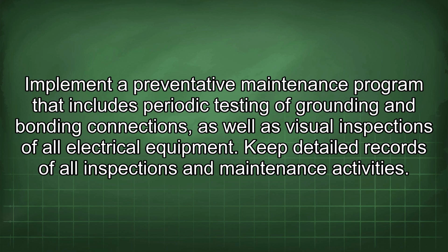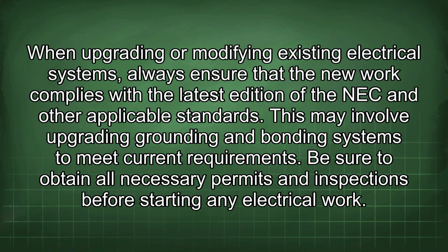Implement a preventative maintenance program that includes periodic testing of grounding and bonding connections, as well as visual inspections of all electrical equipment. Keep detailed records of all inspections and maintenance activities. When upgrading or modifying existing electrical systems, always ensure that the new work complies with the latest edition of the NEC and other applicable standards. This may involve upgrading grounding and bonding systems to meet current requirements. Be sure to obtain all necessary permits and inspections before starting any electrical work.